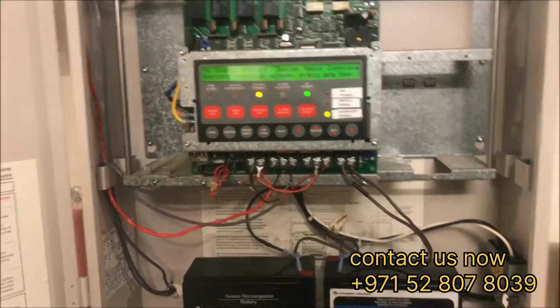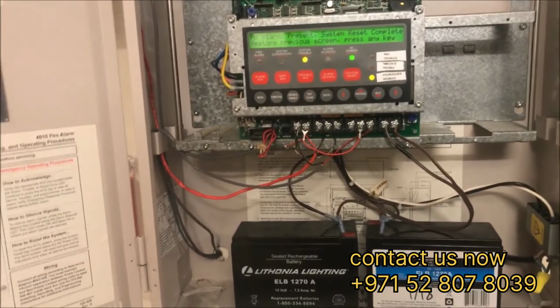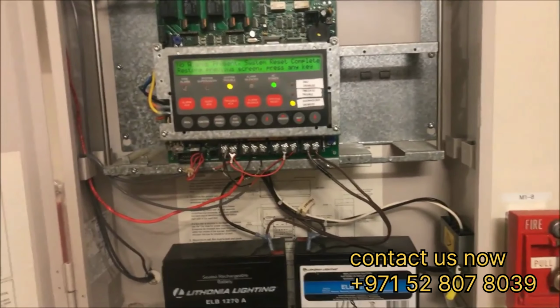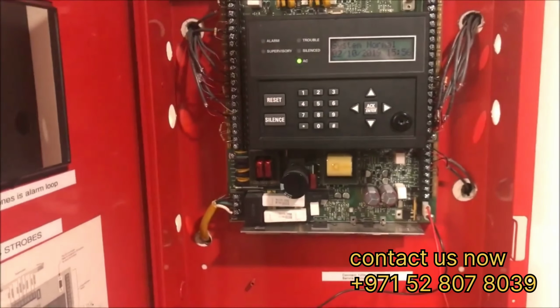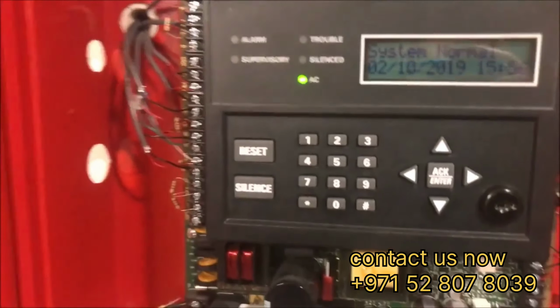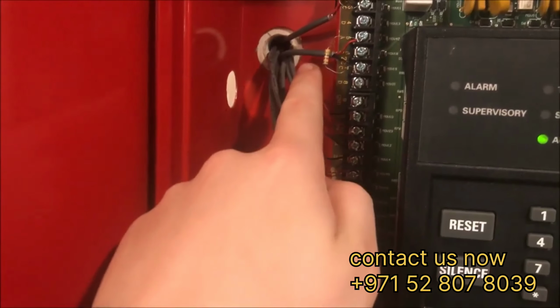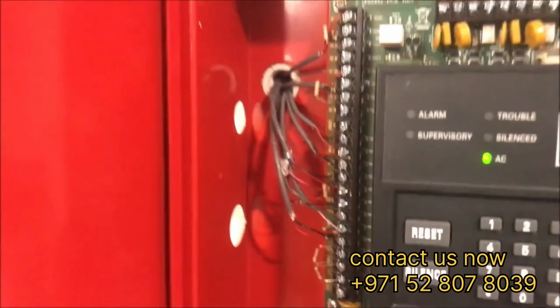I'm trying to think, really, is there anything else? Really, the only difference between an addressable and a conventional panel is the fact that this one just listens for a closed circuit. And one of the things is supervision. It supervises through a resistor, looking for that small trickle to come back.